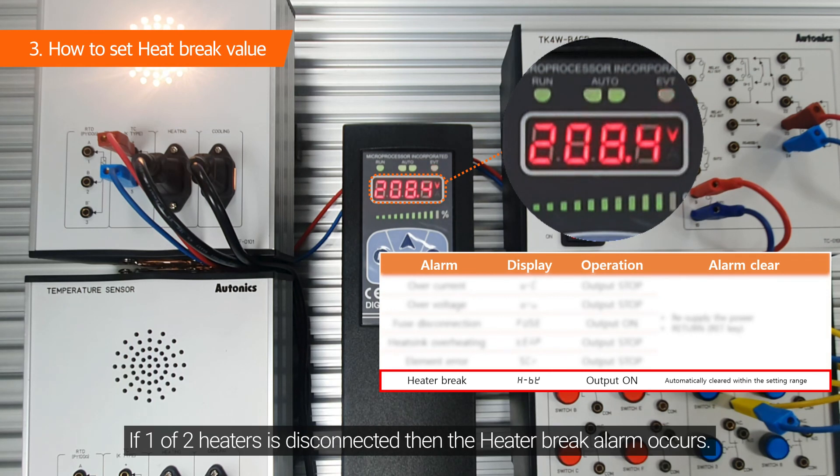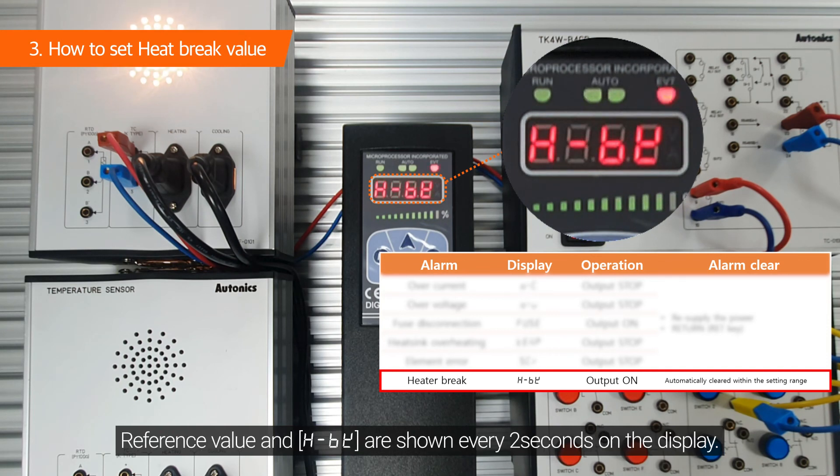If one of the two heaters is disconnected, then the heater break alarm occurs. The reference value and H-bE are shown every two seconds on the display.